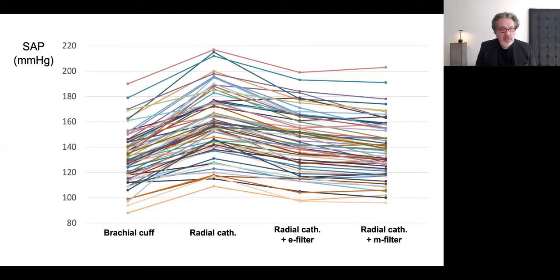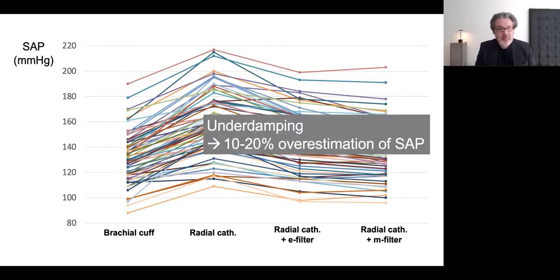So here are the results. On the left-hand side you have the systolic arterial pressure measured non-invasively with the brachial cuff, then the systolic arterial pressure measured with the radial catheter—and once again, all these patients had, by definition, an underdamped radial pressure waveform. Then you see the systolic arterial pressure values with the electronic filter and with the mechanical filter. You can see that underdamping was, on average, responsible for a 10 to 20% overestimation of systolic arterial pressure.